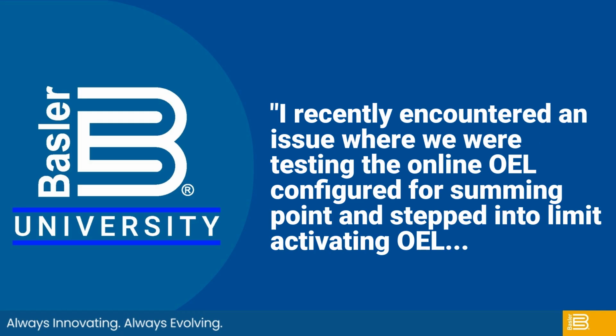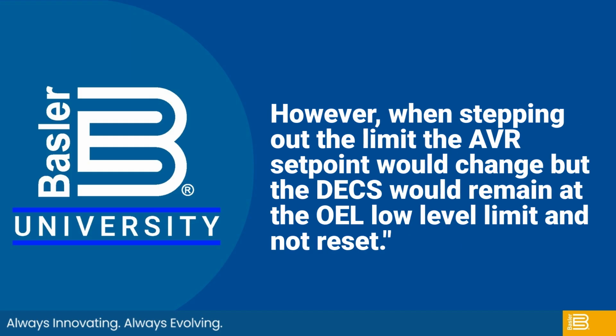Recently encountered an issue where we were testing an online OEL configured for summing point and stepped into the limit, activating the OEL. However, when stepping out, the AVR set point would change, but the DECS would remain at the OEL low level limit and not reset.